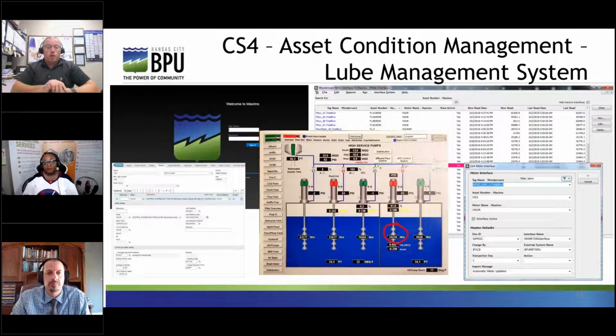Case study 4, CMMS and SCADA driving oil analysis. For the longest time, oil in our large medium voltage motors was changed on calendar year from installation regardless of operating condition or oil condition, which is what the motor O&M says to do. The oil was changed, and that needed to be changed.